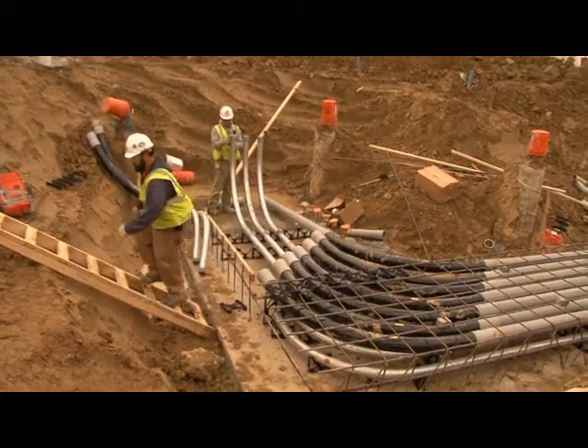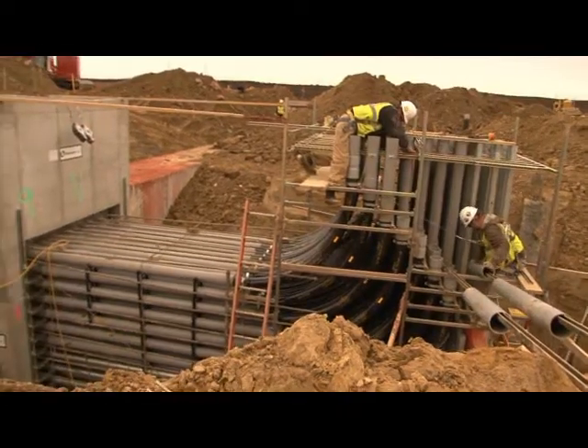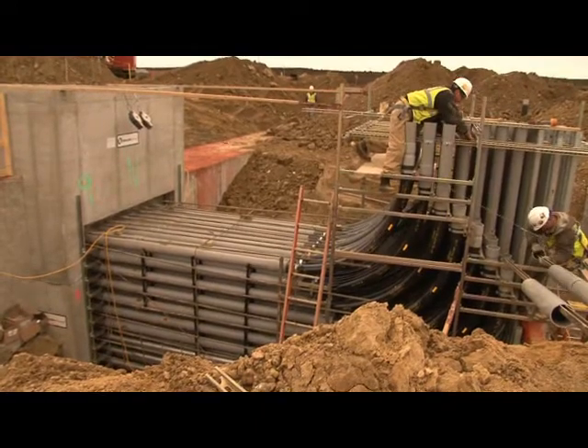Volk says the wires may be fed through the conduits using vacuum. Manholes, like you see at the left of the screen, serve as easy access to the duct bank. Manholes are basically used as a junction between the conduits. Sometimes if you get a really long run with a lot of bends and angles, it's very hard to pull, so we put in manholes to help transition from one conduit to a different area of the yard.